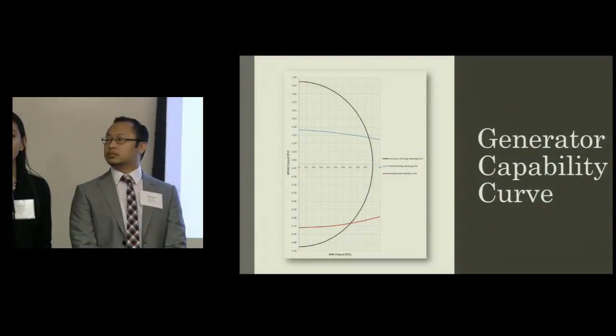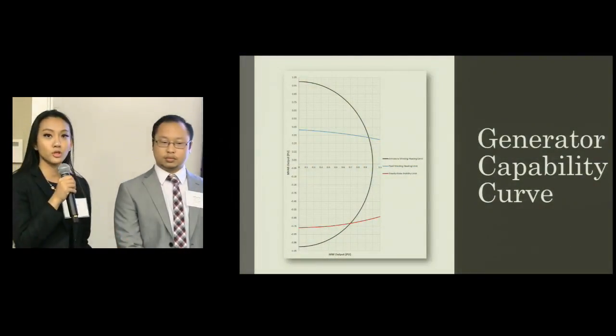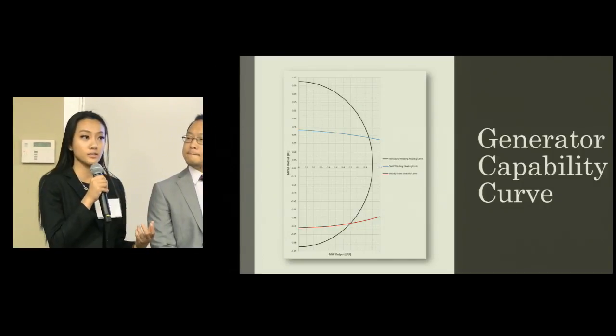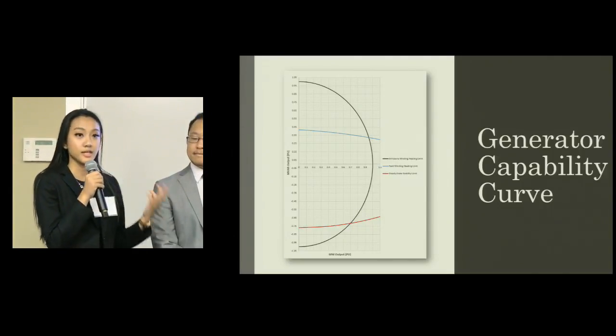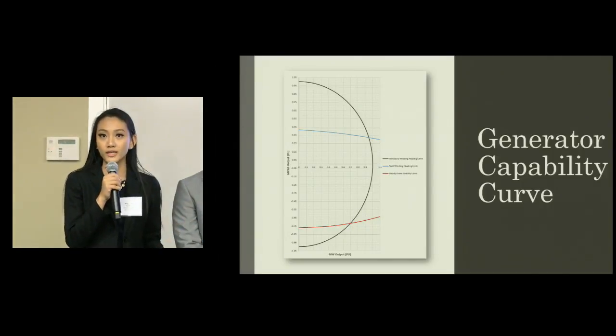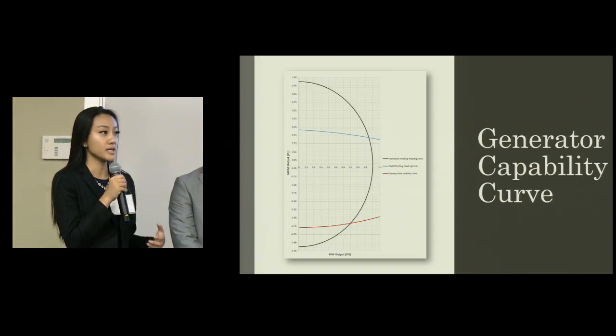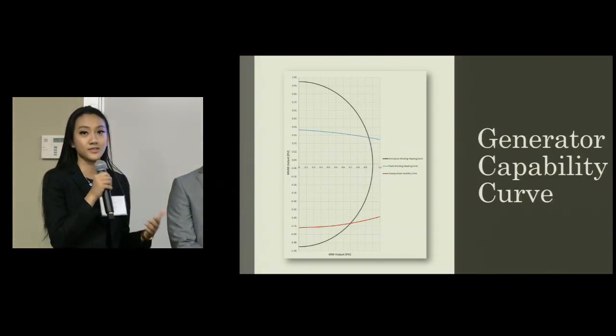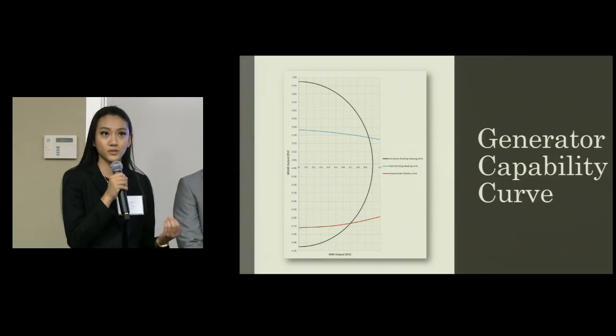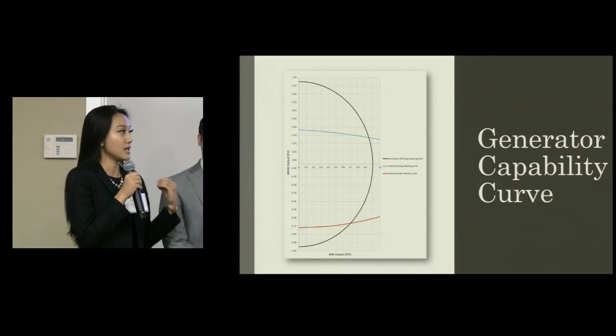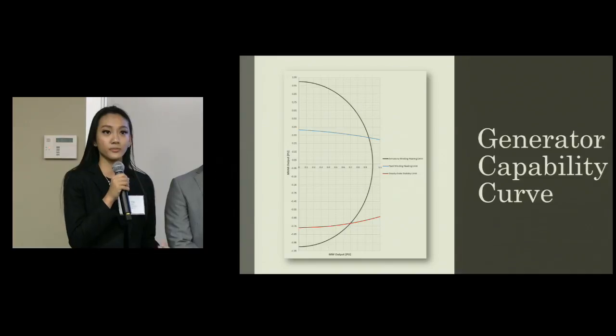The generator capability curves make up the safe operating regions of a generator. The armature winding heating limit corresponds to a heating limit for the coils in the stator. Likewise, the field winding heating limit corresponds to the coils in the rotor. And lastly, the steady state stability limit corresponds to the physical components of the generator. It will protect the generator from losing synchronism with the grid or even slipping a pole. And these 3 curves here make up the generator capability curve.